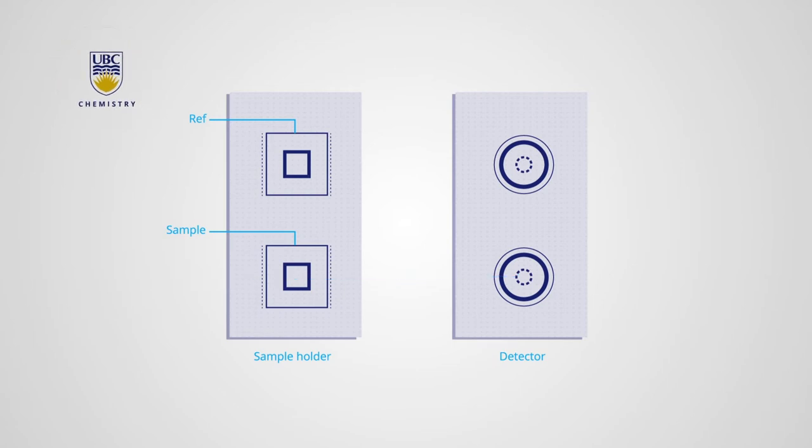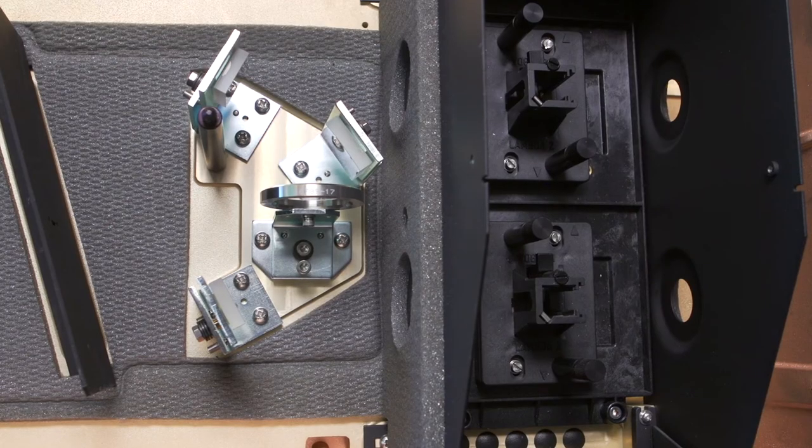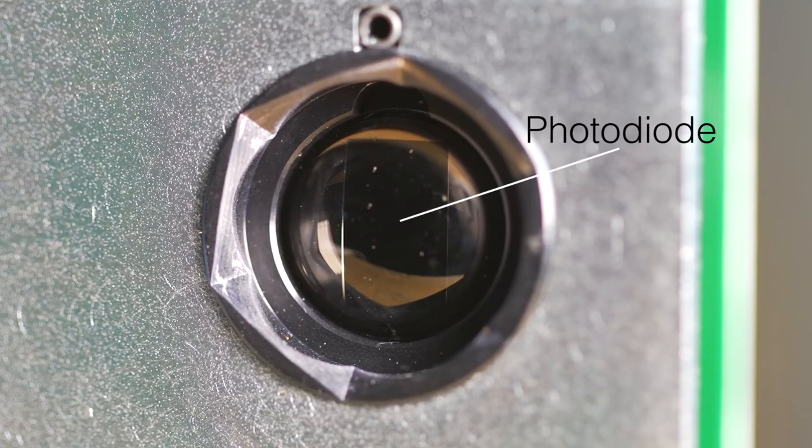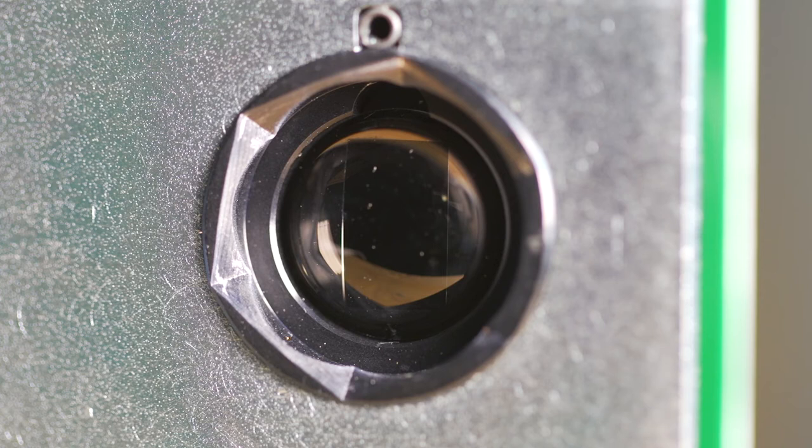Each light beam continues onto a detector. The detector setup in this instrument is a bit unique. It uses two photodiodes instead of the more common and more expensive single photomultiplier tube, or PMT. The reference and sample beams strike different detectors, while a PMT setup would use a chopper and then recombine the beams onto one PMT. In both cases, the signals are digitized and sent through electronics to a computer.